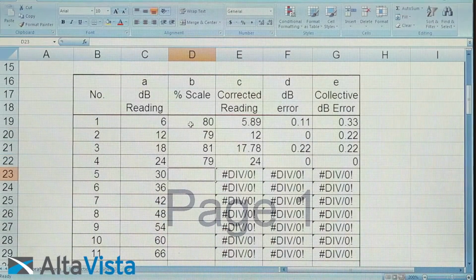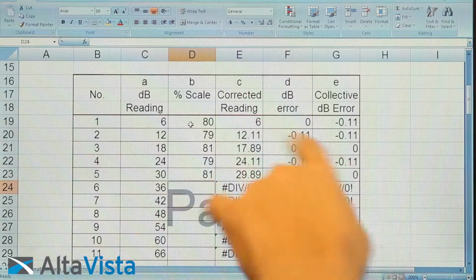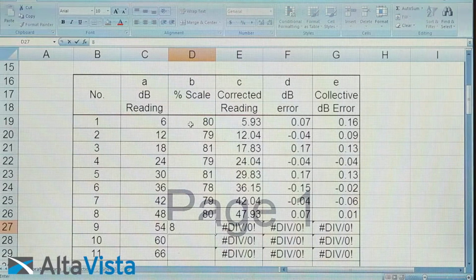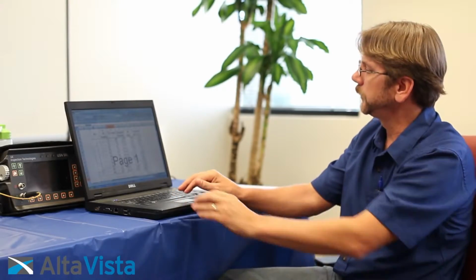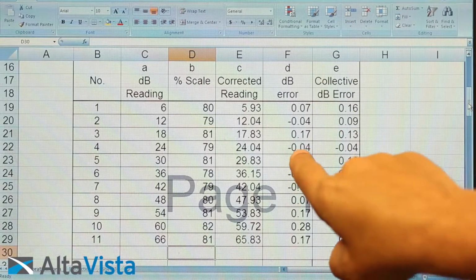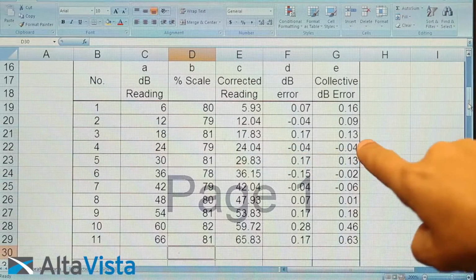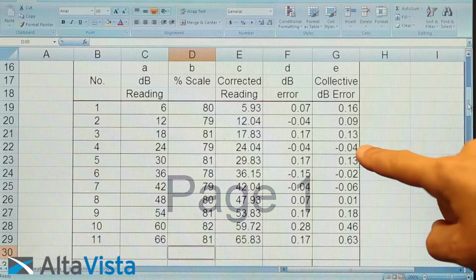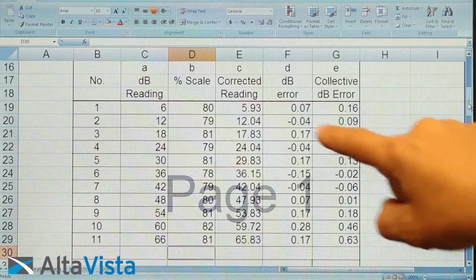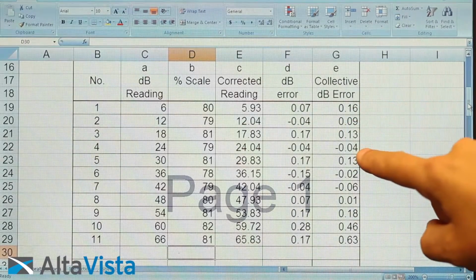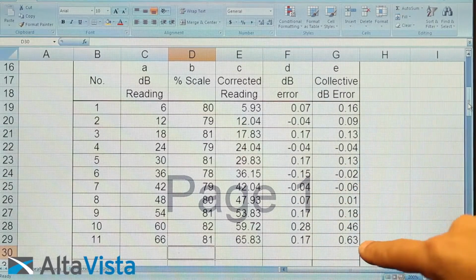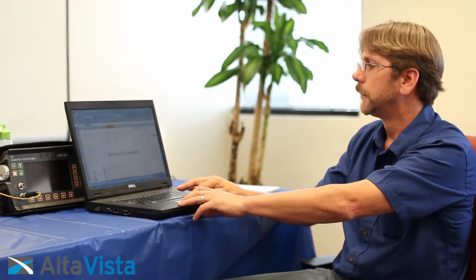As I input the values, after we get several values in there, it will start to calculate the dB difference. As you can see, it starts to do the dB error and the collective error. And that's where it completes. It's important to note here that you take the closest value to 0 and make that your starting point. So I've highlighted this particular cell, and this collective error is our 0, or our starting point. For the collective dB error, it will add these together as you go up, and as this is the starting point, it will add these cells together as it goes down. And that plots a graph on the next page.